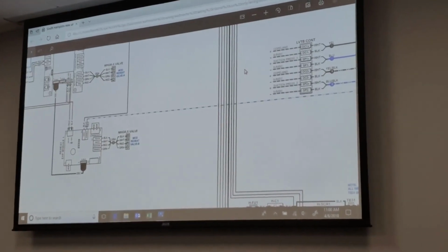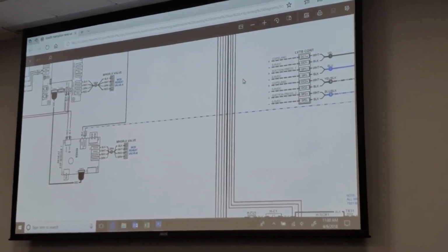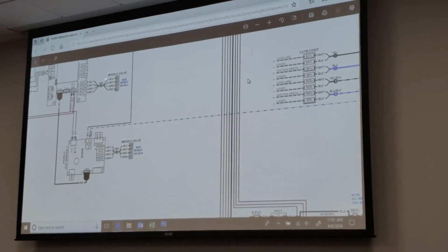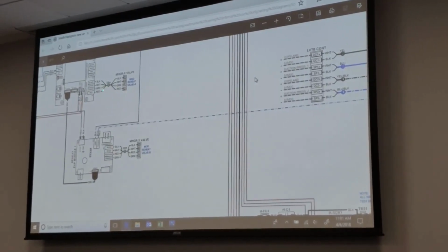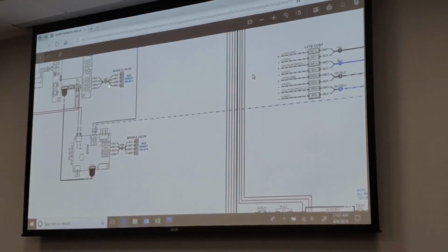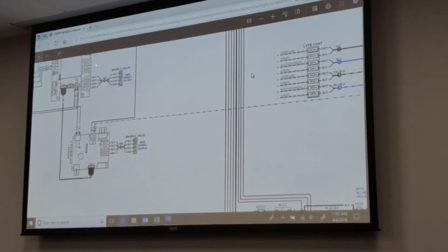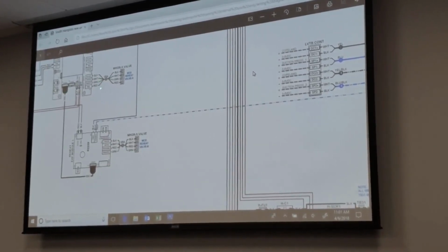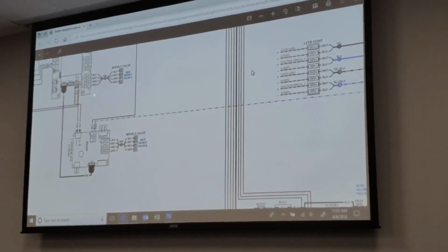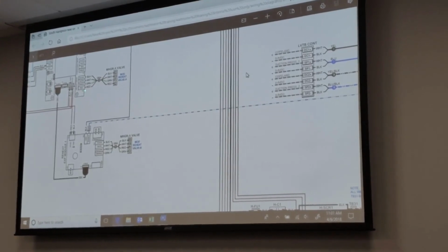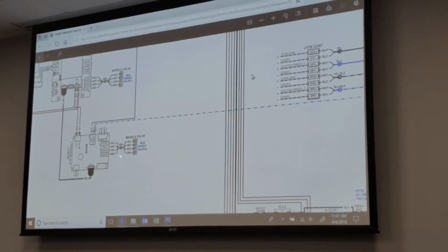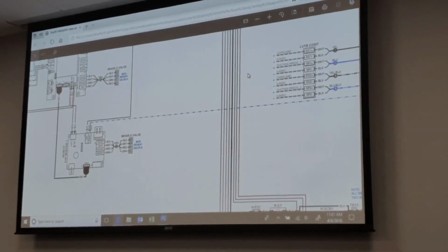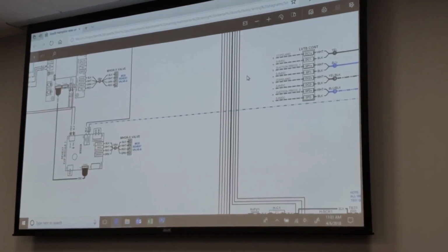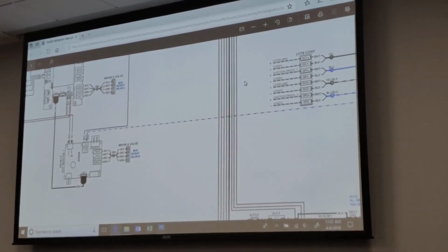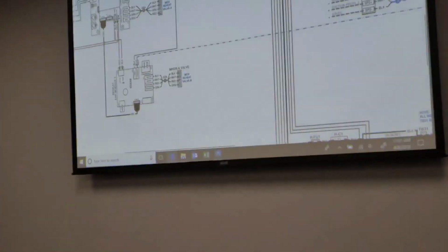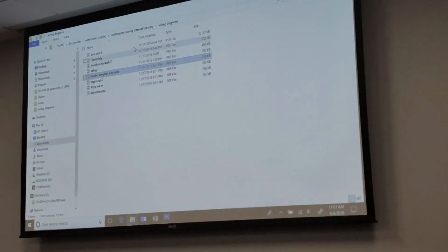Once they finally sent me the wiring diagram, or sent me a serial number, I could pull the wiring diagram from the internet. I looked at it and said, hey guys, this is wrong. This here is correct. This guy needs to match. So matter of fact, this should be moved up here to the condenser valve, and then you have to swap the red and the green. They hooked it up to the wrong drive. This is for the reheat valve. This is for the condenser valve. That's correct. That's wrong. That needs to be moved up there, and then 2 wires need to swap. Like I said, these are things that we've caught in the field, something you come across.